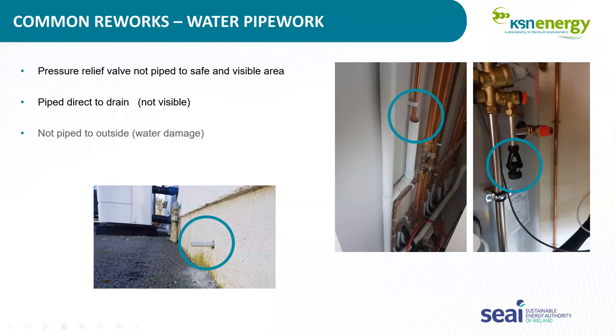Just with regards to that one, like your overflow pipe, you have to be able to see it. Heating systems don't like fresh water, and if water is being lost through the safety valve, fresh water is going to come in. I've seen it in the past where a heating system was fitted and the radiators only lasted a year. They've rotted from the inside out. So it's important that if there is an issue and the safety valve is blowing or dripping or whatever it is, that the homeowner can see it.